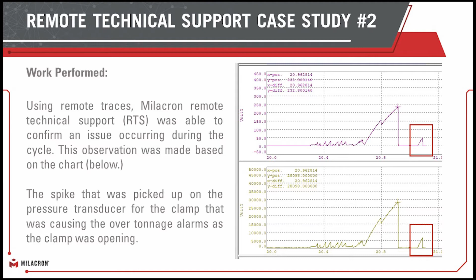So with this understanding, and again with this knowledge, our techs were able to work with the customer, eliminate a few potential items, and get down very quickly to a connector or cable issue. After working with them and tracing through where that line wiring goes back through the clamp back up to this particular item, this transducer, we were able to locate with the customer a broken pin actually in the circuit. So something as simple as movement had caused a pin to come loose out of a connector, and fractured the pin. So every time it would get to a certain position, it was causing that pin to hit a certain way, and causing the signal to increase and make it look like there was an actual issue.